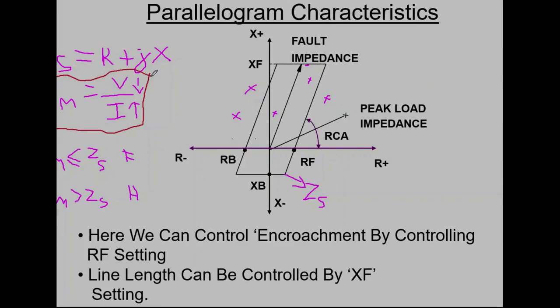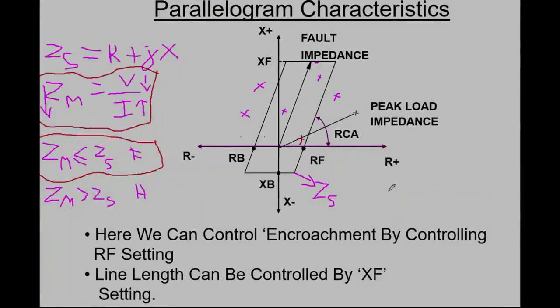Then imagine the amount of starting current that is going to be absorbed. During that time, there will be a suppression in voltage and an increase in current, which will result in low impedance. And if this happens, you may end up in this scenario. This scenario means you will plot something inside. If you plot something inside, what happens? The relay will trip. If the relay trips, you will never be able to start your locomotive. Therefore, the concept of differentiating between a starting of a locomotive and a real fault comes into the picture.